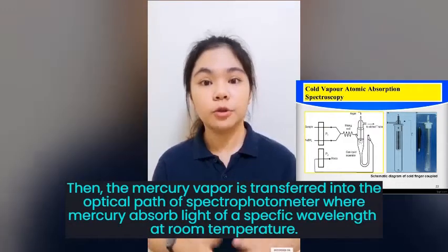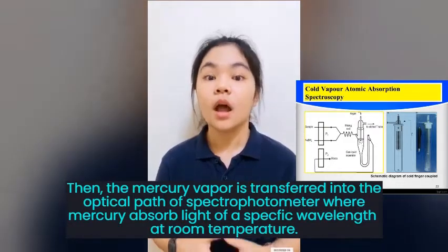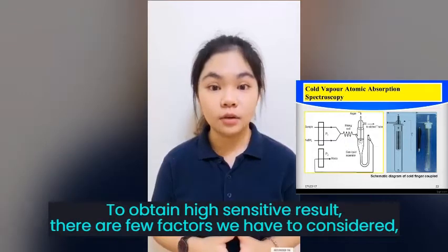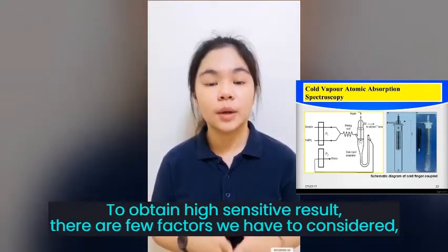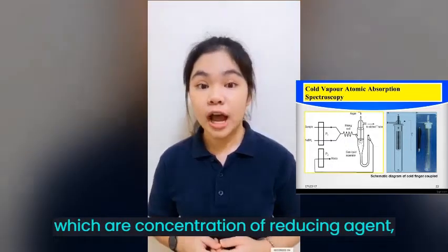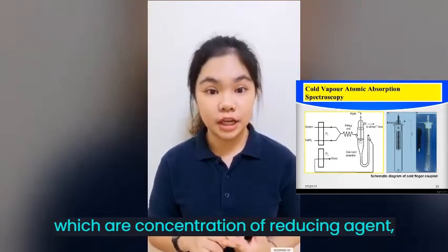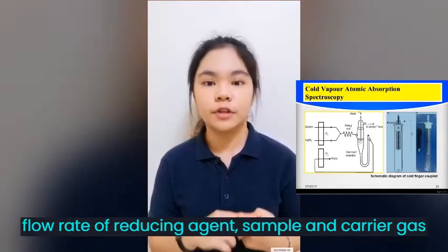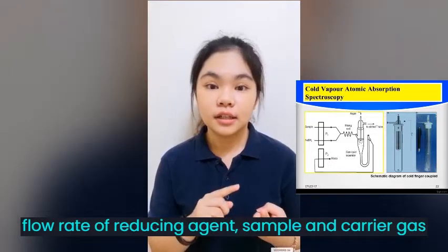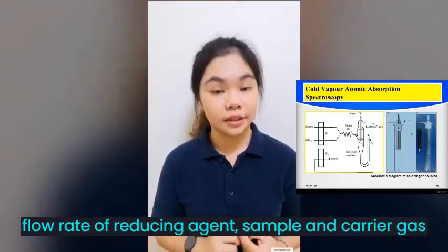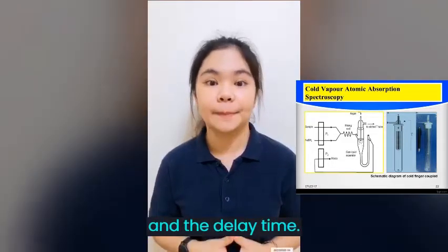mercury absorbs light of a specific wavelength at room temperature. To obtain highly sensitive results, there are a few factors that we have to consider, which are the concentration of reducing agent, the flow rate of reducing agent, the flow rate of sample and carrier gas, and the delay time.